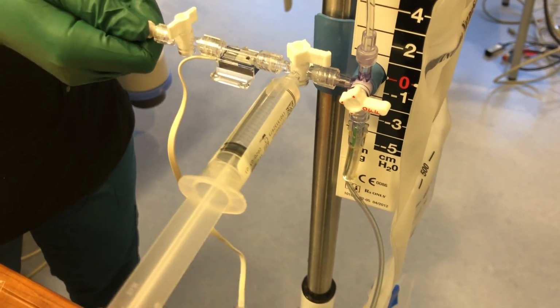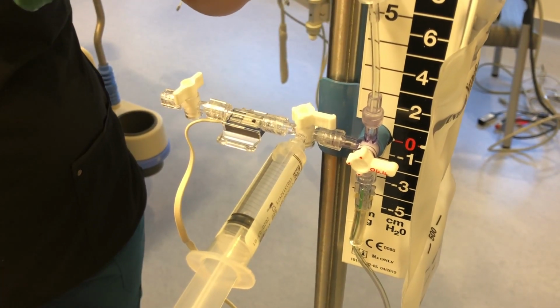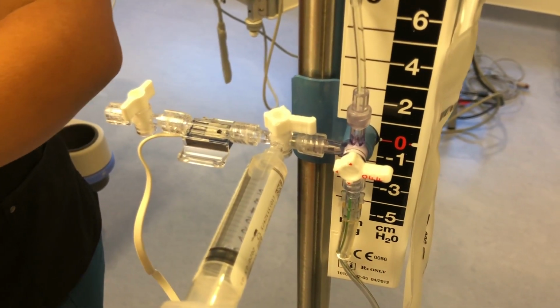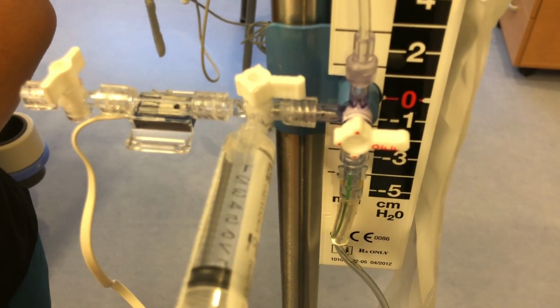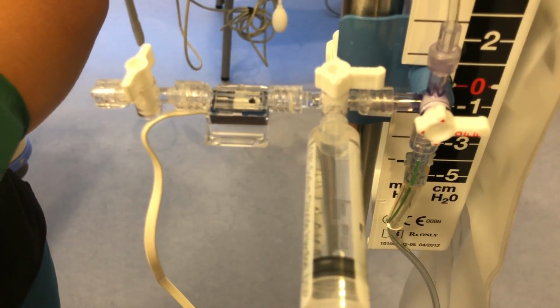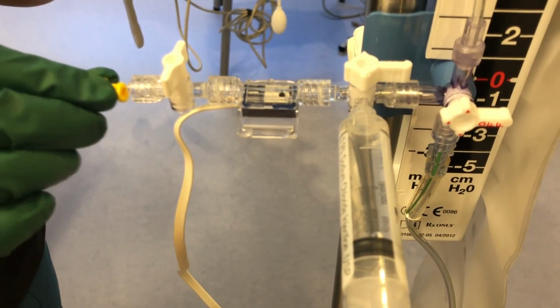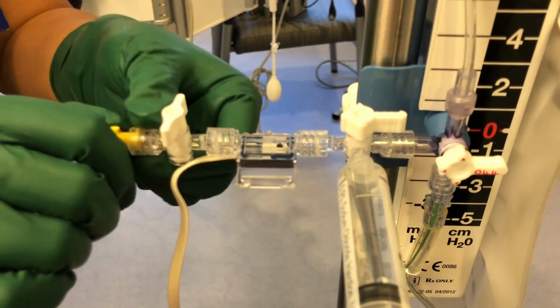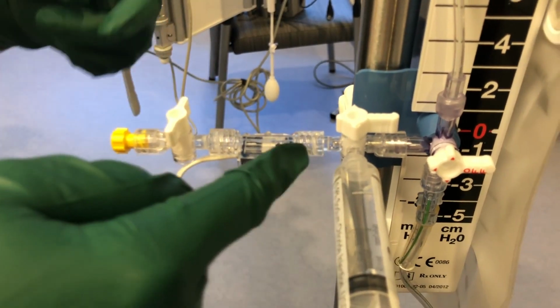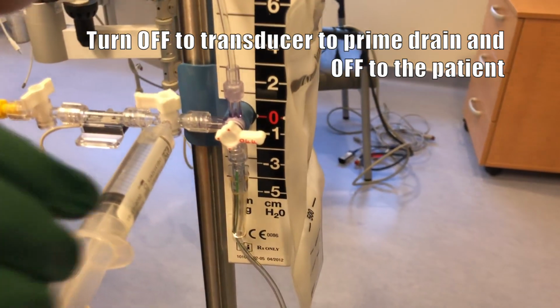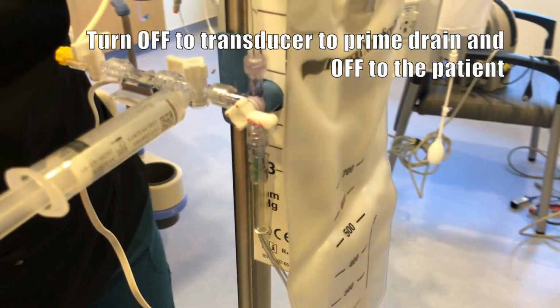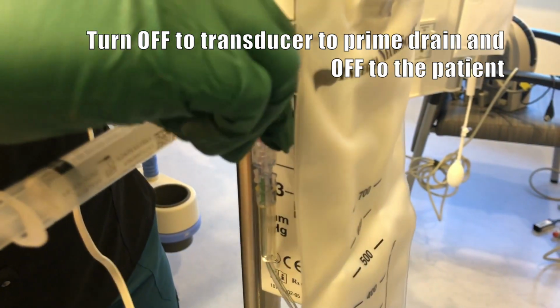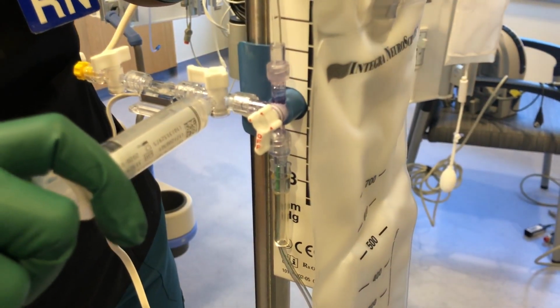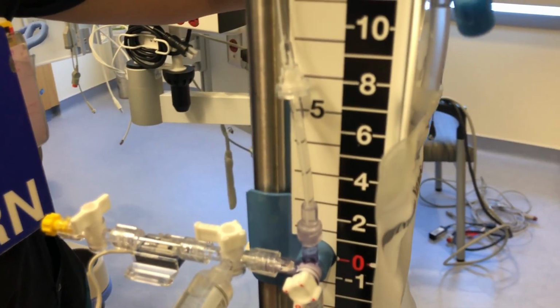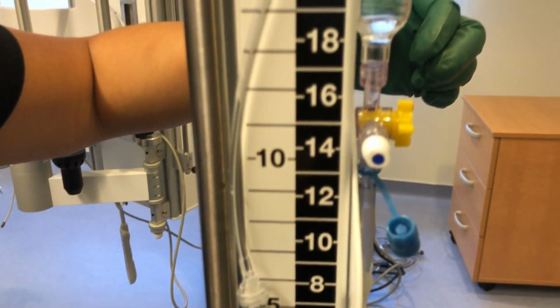You will change out this white port with a yellow cap. What's this one? So this side is primed. Now you're going to prime the drainage system itself. So turn it off to the transducer, and you can prime it towards the drainage system first. So off to the patient. Go ahead and prime all the way through. Make sure there's no air bubbles.